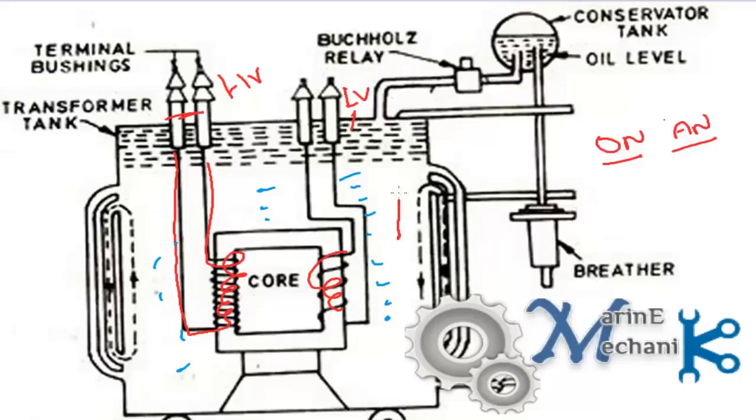Oil which is getting heated up due to the transforming action — the hot oil goes higher in level and the cold oil comes down. So the hot oil enters the air cooling fins and gets cooled and then it goes down. There is a natural circulation of the transformer oil, cooling the transformer winding by air natural action. That's why it is called oil natural and air natural cooling.